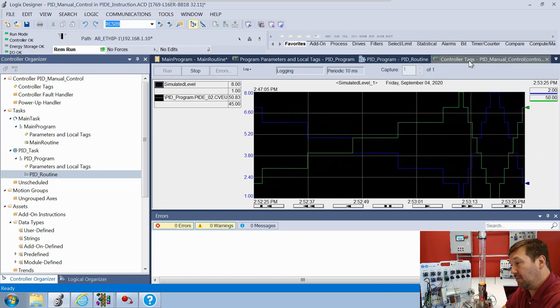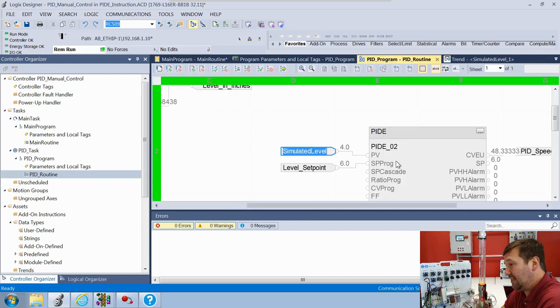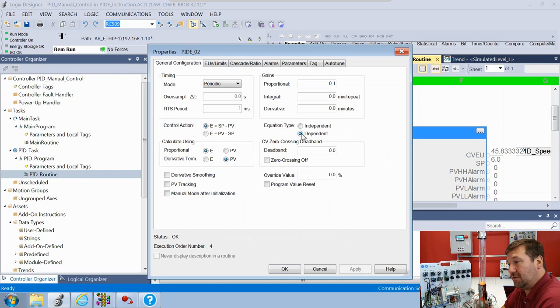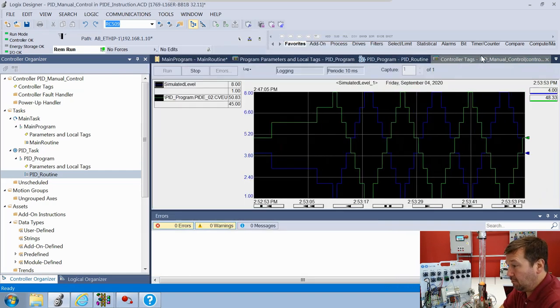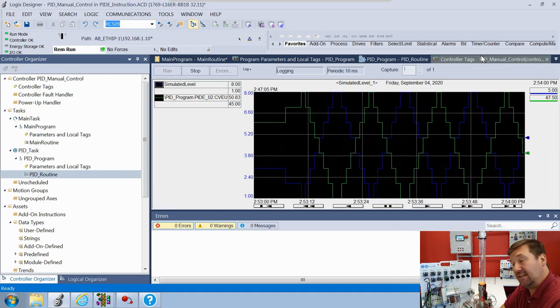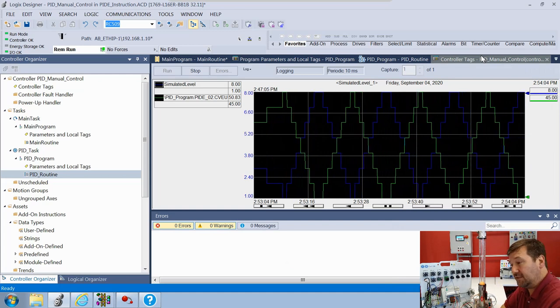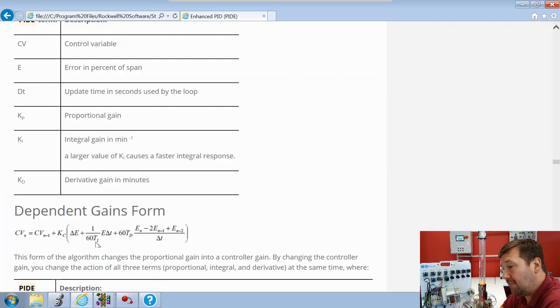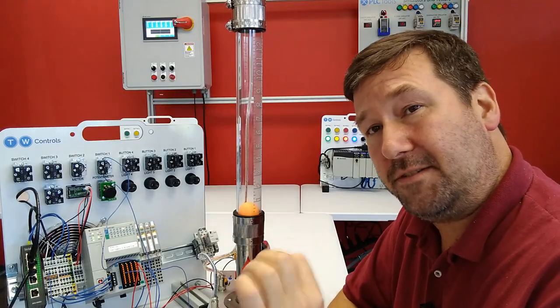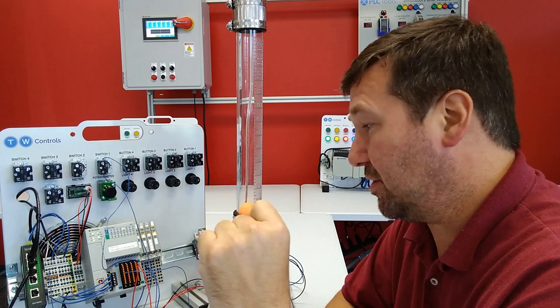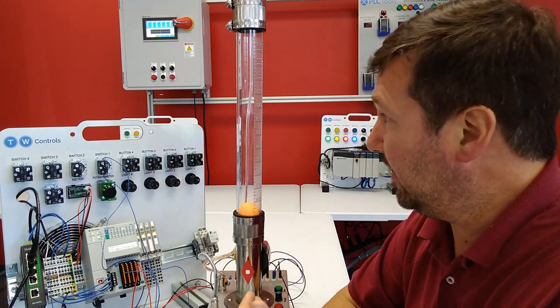Now let's talk about the independent and dependent equation types as far as the proportional change. Let's open up our PIDE and switch from the dependent equation type to the independent equation type. If you watch the trend, you'll see it made no difference in the change to the process variable - either the amount or the frequency - because right now we have our integral and our derivative at zero. When you work the dependent equation compared to the independent they come out the same.